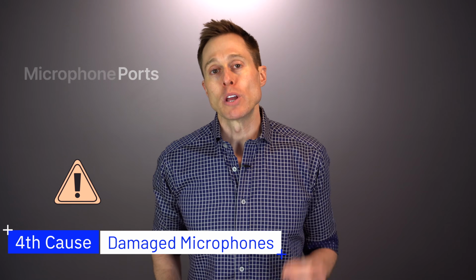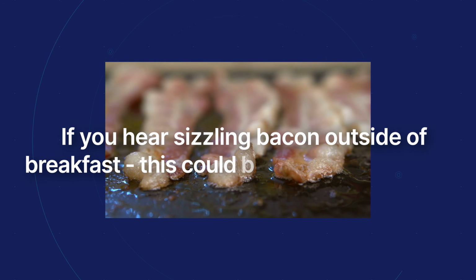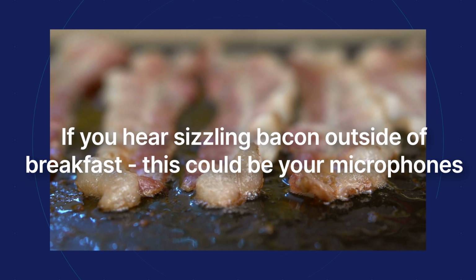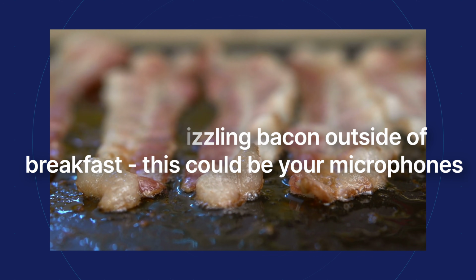There are anywhere between 1 and 4 microphone ports on any given hearing aid that allow sound to hit 1 or 2 microphones inside of the device. You can often identify if one of the microphones is actually damaged because you'll hear static noise that sounds a lot like sizzling bacon. This often occurs if you stick an object inside of the microphone port and rupture the microphones, or if you get a jet stream of water hitting the microphone in exactly the wrong way, like if you were to jump in the shower.